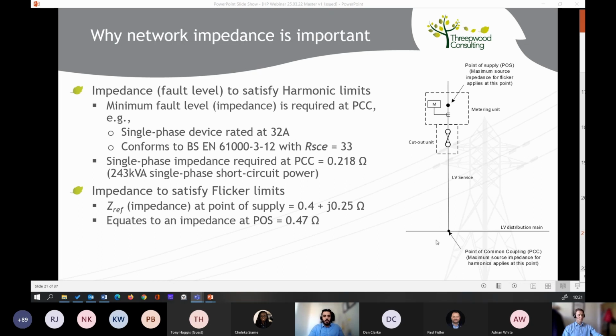Yeah, that's correct. But then you also have the requirement for flicker, which for a single phase device is 0.4 plus J0.25, which equates to 0.47 ohms at the point of supply in your homes. So we've got to make sure the cable is big enough to handle that impedance.